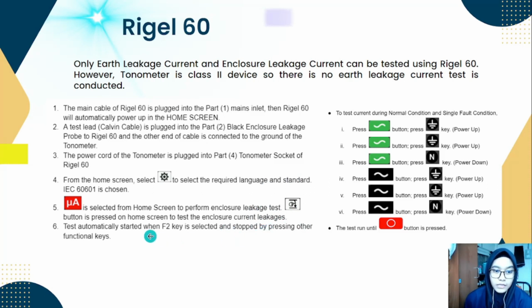Then the test will automatically start when the F2 key is selected and stop when pressing the other functional keys. So to test the current during normal condition and single fault condition, this is the sequence that we can follow. Then after we follow all these conditions, we can press this button to finish the test.